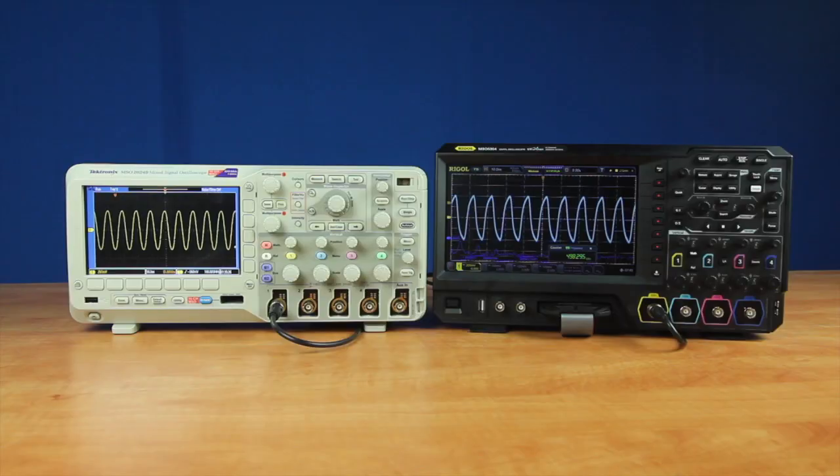So let's take a look at the Rigol. On the Rigol we've connected the trigger output function into the digital logic line so we can use the counter here to see how many triggers it takes per second.